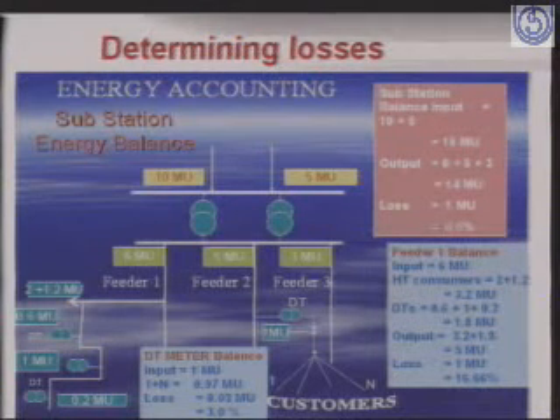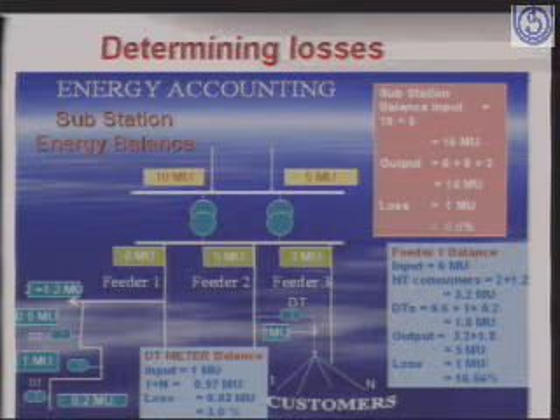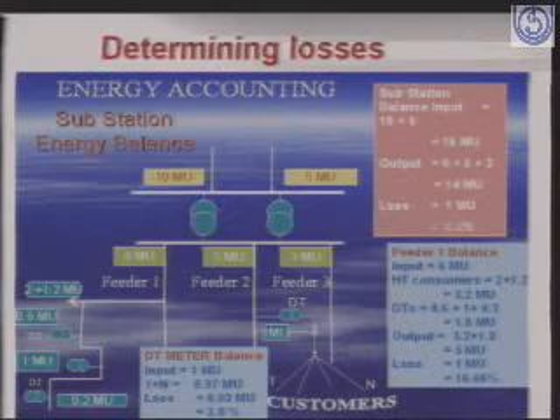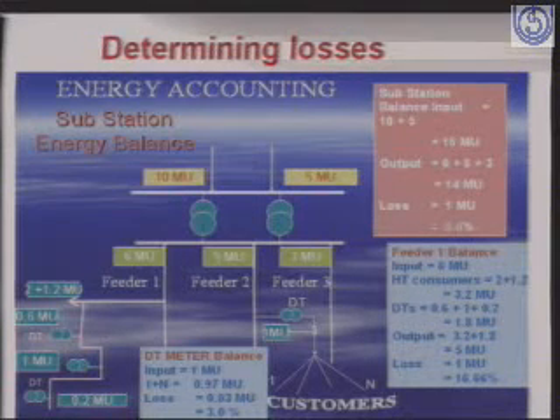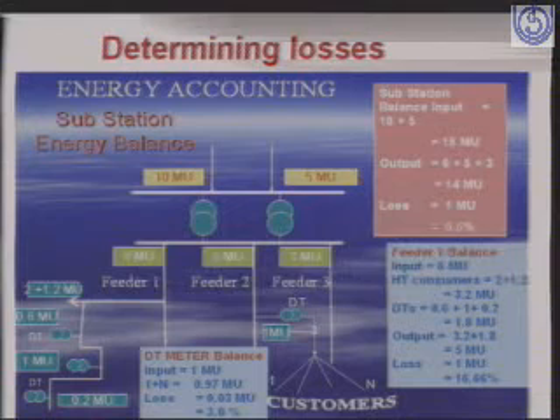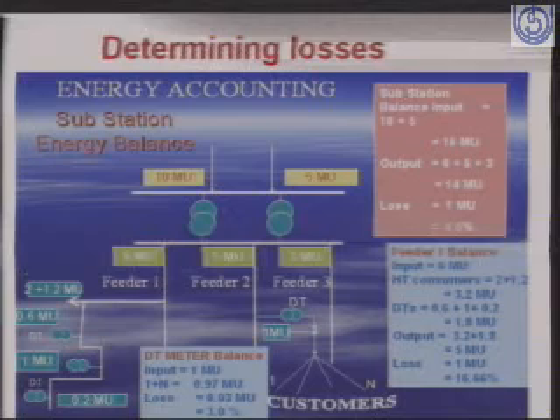Then we have a distribution transformer from where 0.6 million units are being dispatched. Then we have another distribution transformer from where 1 million units are being dispatched, and there is a third distribution transformer also where 0.2 million units are being dispatched. If you club all this, then we can find out what has been dispatched and what has been received. In this particular case, the total loss comes to 1 million units. 6 million units have been received and 5 million units have been the output, so loss is 1 million units, which accounts for 16.66%.